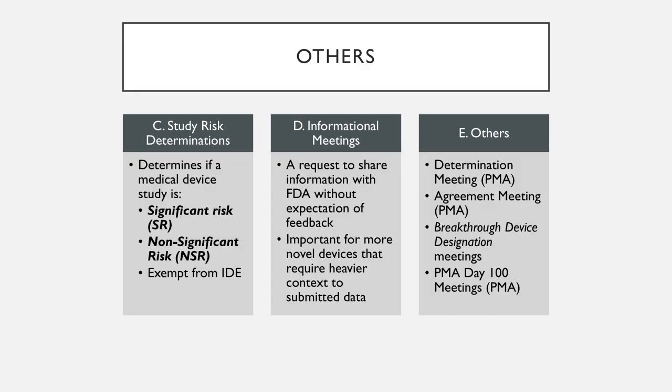There are even certain meetings, such as the breakthrough device designation meeting. If your device qualifies as something novel enough to be considered a breakthrough that has a high potential to help a lot of people through potentially less rigorous means, if you qualify through the breakthrough device designation process, you can have expedited meetings with the FDA, quicker turnarounds on data, or the pre-submission process. Very helpful and applicable to any medical device startups that don't have the funding to wait for a typical one-year or six-month turnaround on any data that they submit.